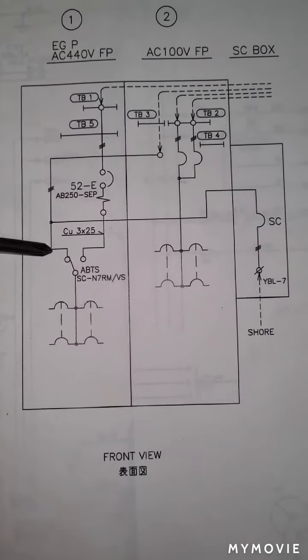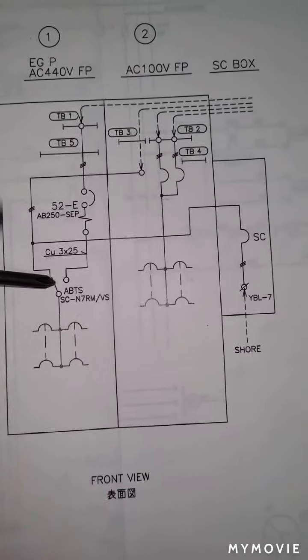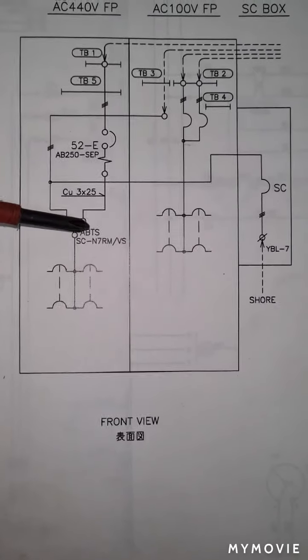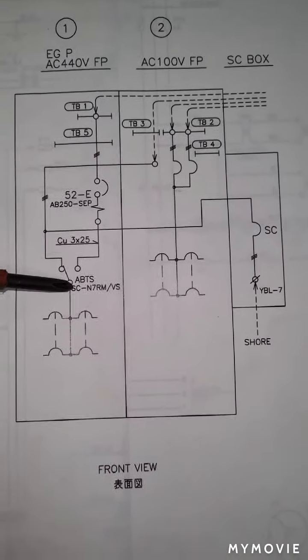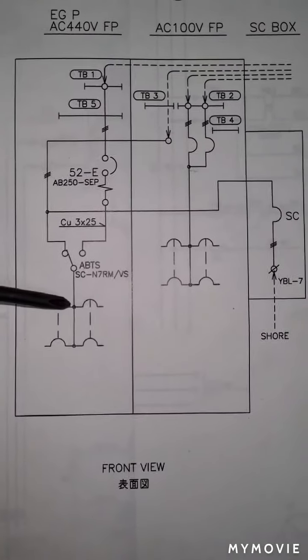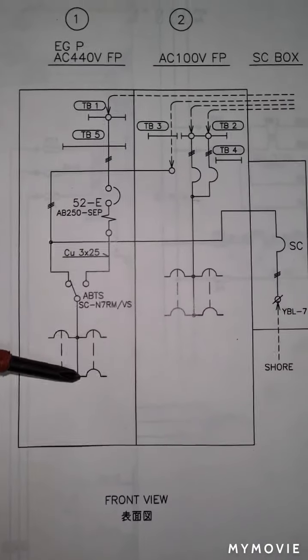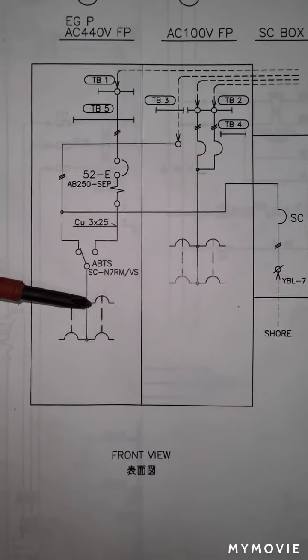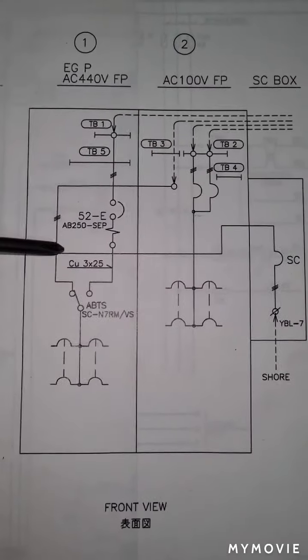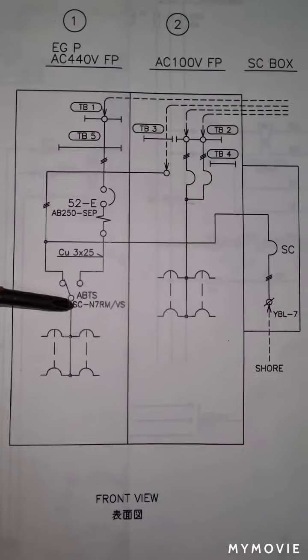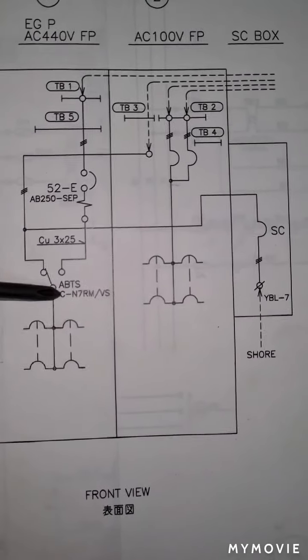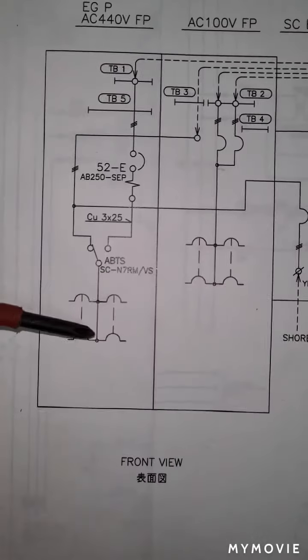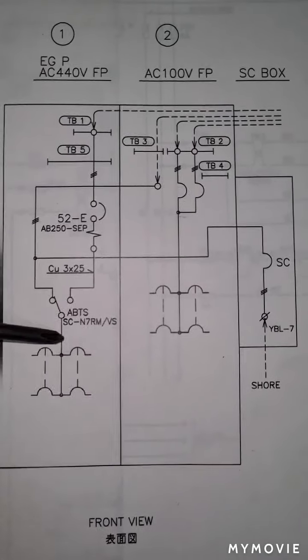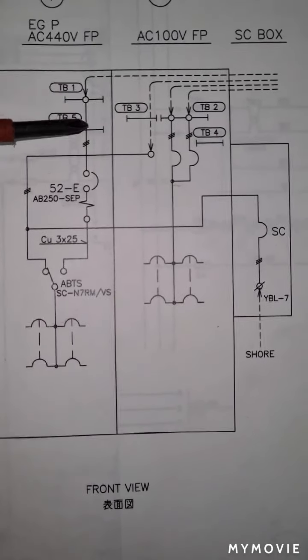Also, from these termination points, there are two magnetic contactors. These two magnetic contactors are known as the automatic bus transfer switch. When this is in position here, the feeder takes its power from the shore connection or from the main switchboard. But if this automatic bus transfer switch goes this way, it takes its power from the emergency generator. Take note, when the ship already has shore power, the emergency generator is not needed.